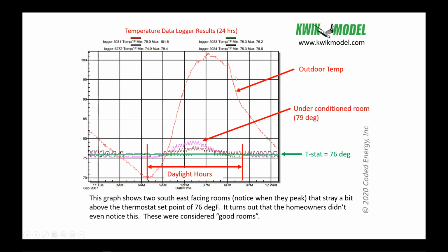So that red line is the outdoor temperature. These other lines are indoor rooms, okay? The green line is the thermostat set temperature. And I told all these homeowners, in fact, I had them sign a little disclaimer saying, I will set the thermostat at a comfortable temperature that I like, and I will not touch it during this test. I promise to leave the thermostat alone during this test, okay? And so whatever that temperature was, I put a green line.